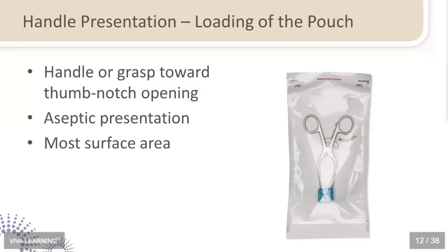This is something that sometimes we just don't think about because we get so used to doing things one way, and there might be a better way or a best practice instead of a common practice. It's suggested that any instruments that have a handle or a grasp, so forceps, hemostats, scissors, an elevator, we should always position those in the pouch so that the handle end is faced toward where we're going to open the thumb notch opening, because that's going to allow us to aseptically present, and it's going to give the clinician the most surface area to be able to grab the instrument to remove it from the pouch or package. So again, handles and hinged instruments should be opened and put toward the thumb notch or opening.